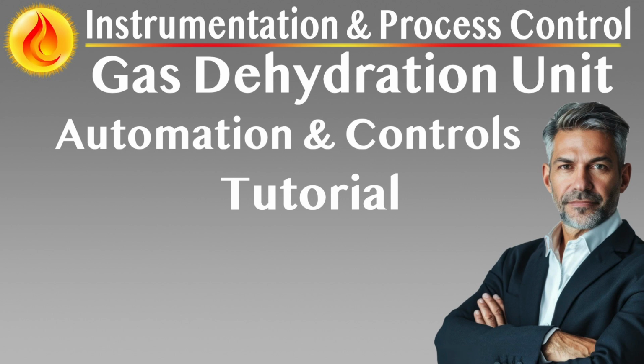Regenerator and reboiler instrumentation. Temperature control. Glycol temperature at reboiler is critical for achieving target lean concentration. Control methodology varies by heating type. Fired heater: temperature control cascades to a fuel gas flow or pressure controller. Hot oil reboiler: temperature cascades to a hot oil flow or heat flow controller. Electric: thermocouple-based PID control. Steam: flow control with pressure reduction and desuperheat as required.